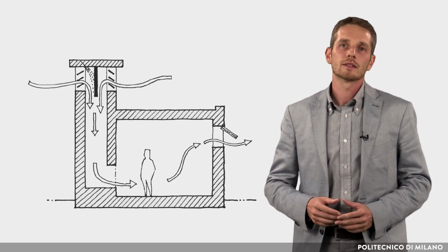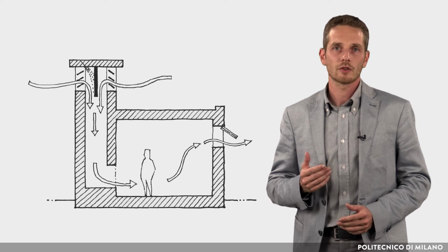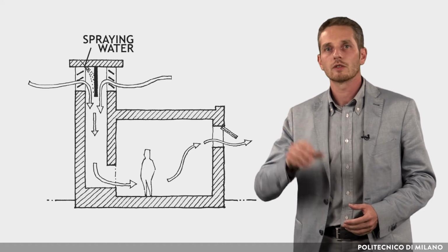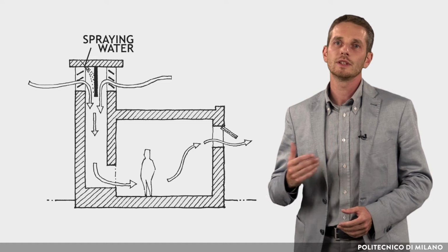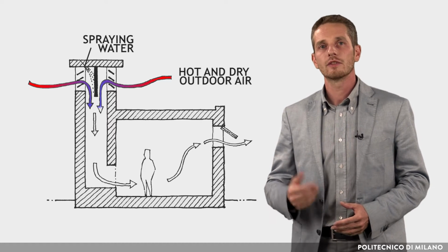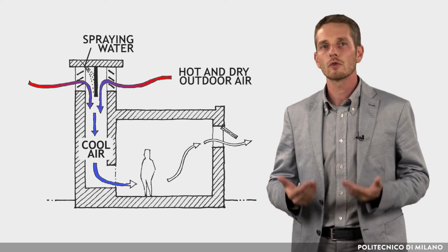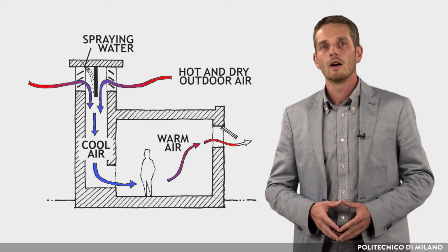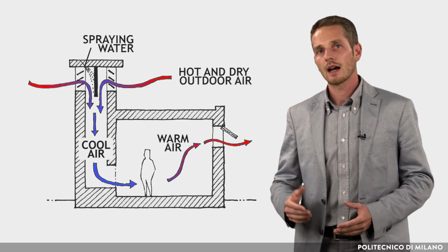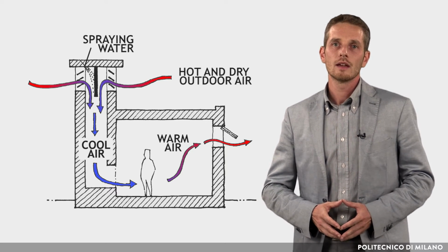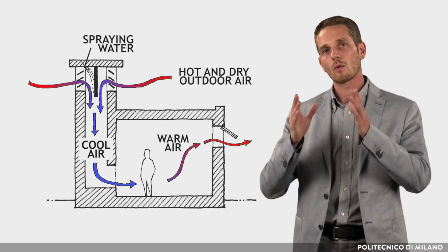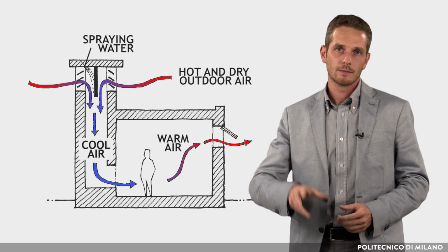In hot arid climates, the adiabatic humidification process, or evaporative cooling, is always effective. Spraying water into a stream of air cools and humidifies it. In very hot, dry climates, this physical phenomenon can be used to improve environmental comfort. One way to take advantage of this physical principle and at the same time to facilitate a good ventilation is to cool the air by adiabatic humidification sinks in a tower and spread it into the space.